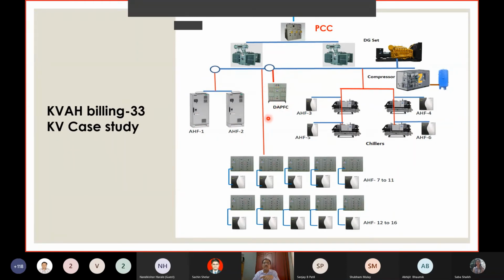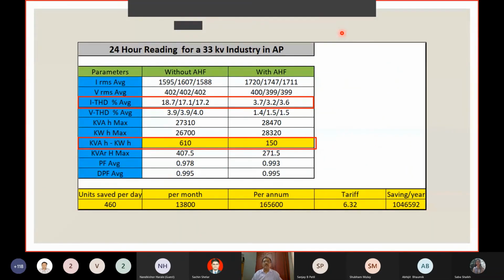So apart from the detuned APFC originally conceived and put in the plant, we had to introduce so many active harmonic filters in order to prevent failure of PCBs, bring down the harmonic across the cross section of the network, and also reduce the harmonic at the point of common coupling level from something like 18% to less than 5%. So see the results. This is the result. Without the active harmonic filters, the THDI was average 18.7, 17.1 and 17.2. And the kVAH for that 1 hour was 610 units.